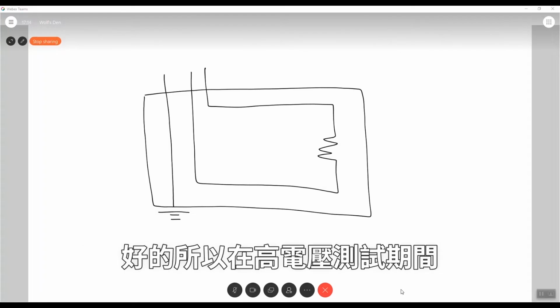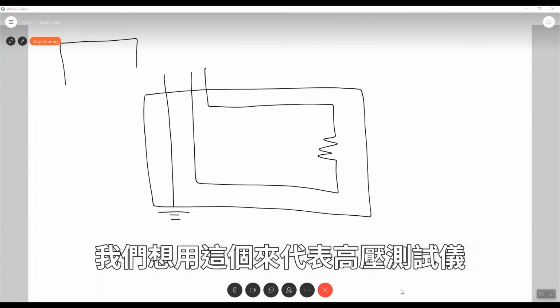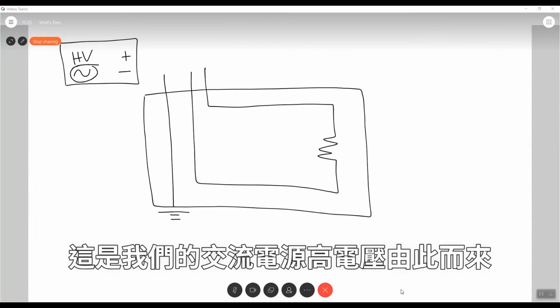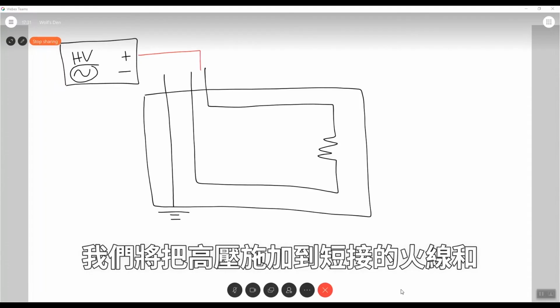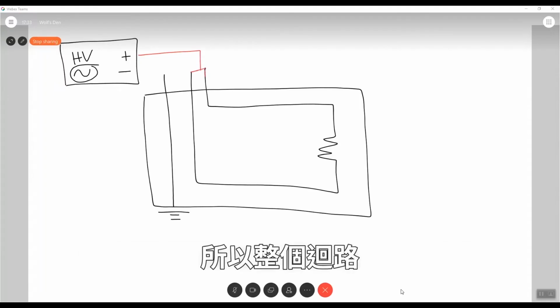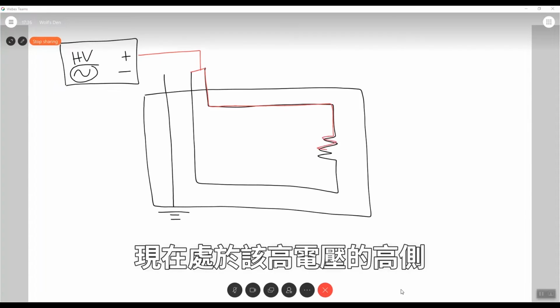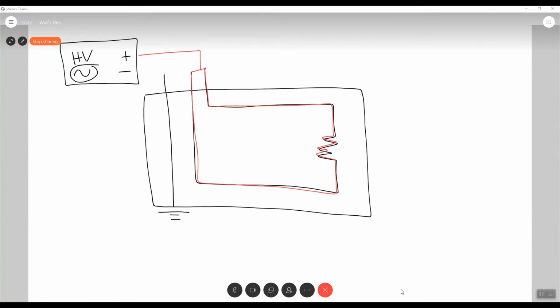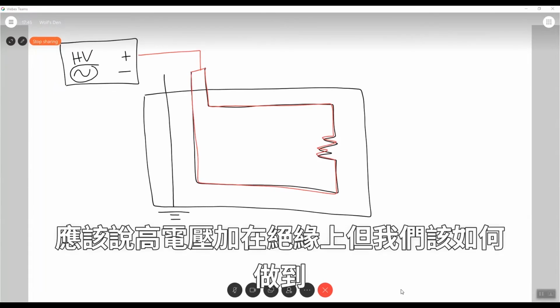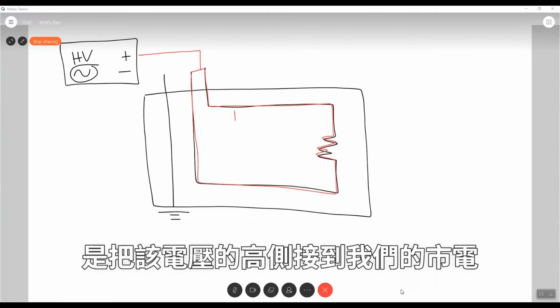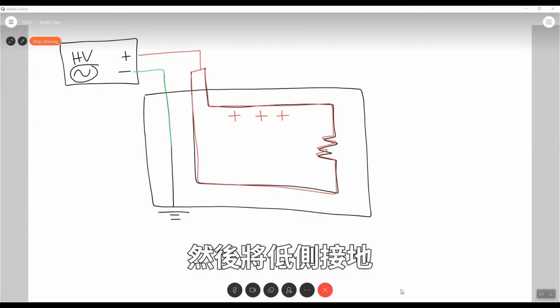Okay, so during a Hipot test, we want to use this to represent the Hipot tester. This is our AC source of where our HV is coming from. We will be sending high voltage to line and neutral shorted, right? So this entire circuit is now at the high side of that high voltage. I shouldn't say high voltage is applied to line neutral. High voltage is applied to the insulation. But how do we do that? By putting the high side of that voltage on our mains and that low side sent to ground.